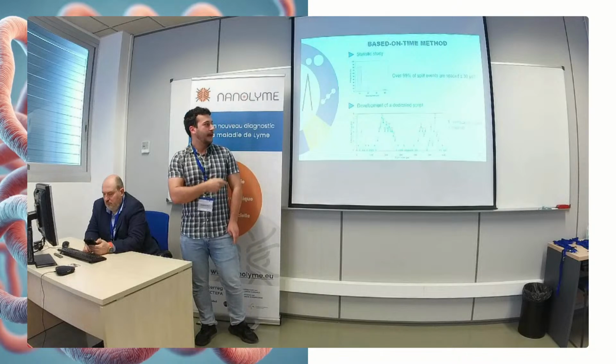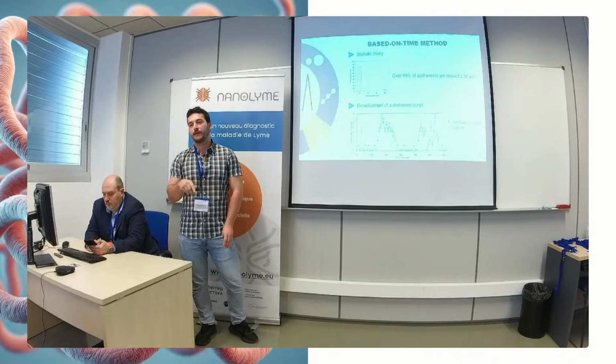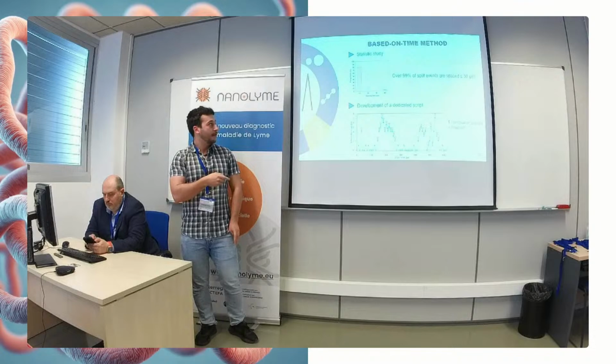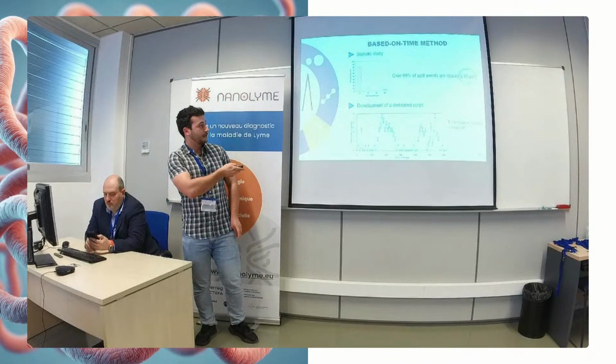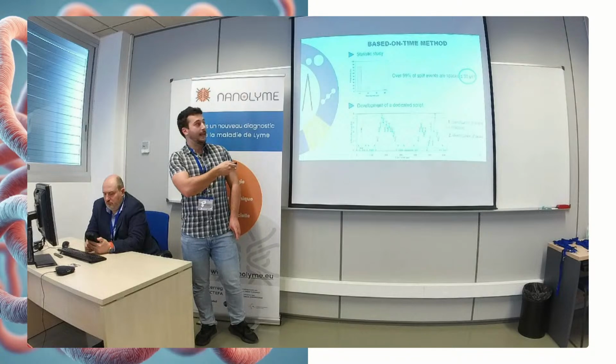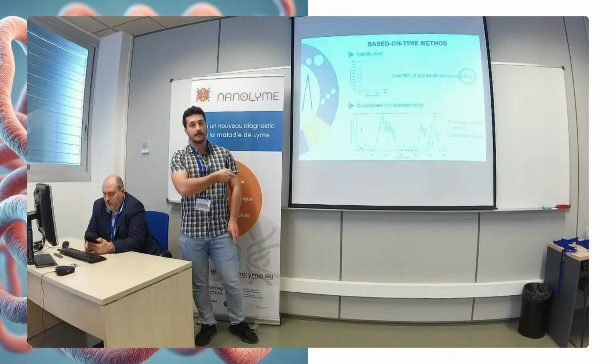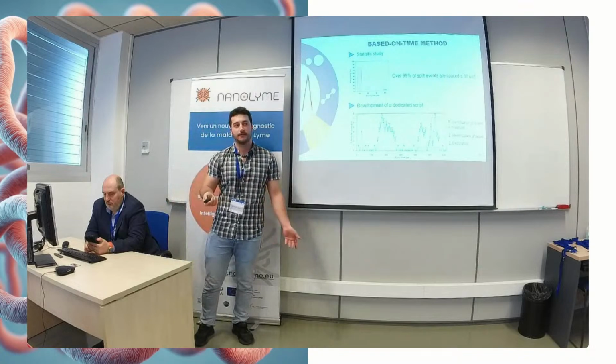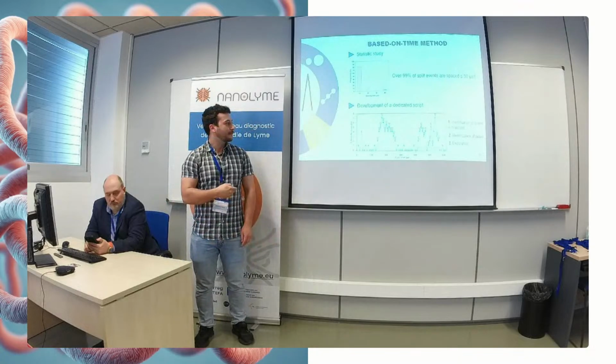First, it will identify all the points above a certain threshold. Then, by looking at those 30 microseconds, if two points are separated by less than this time, it will consider that they belong to the same intensity peak. And finally, we can remove those spikes that in reality are not a nanoparticle, but simply background.